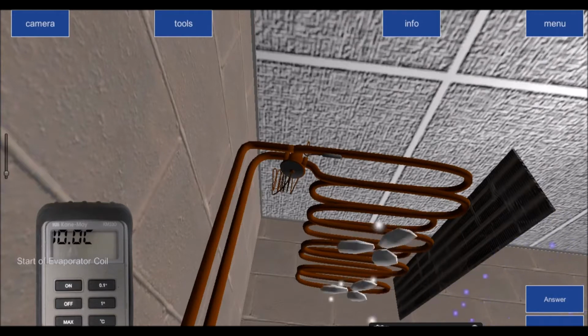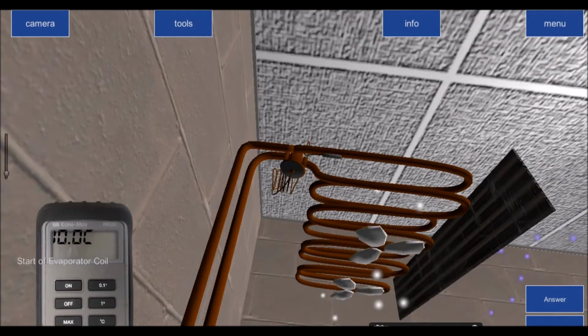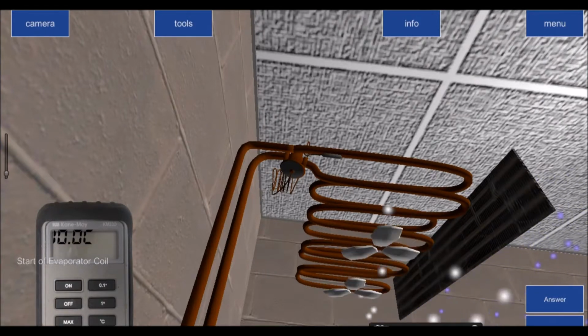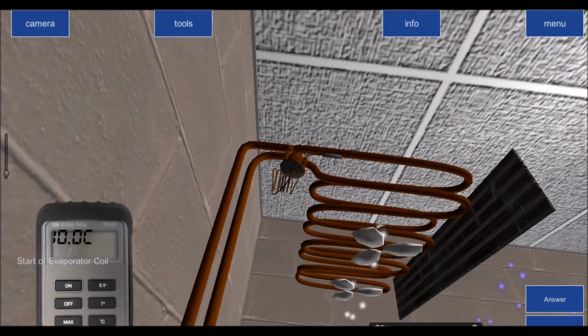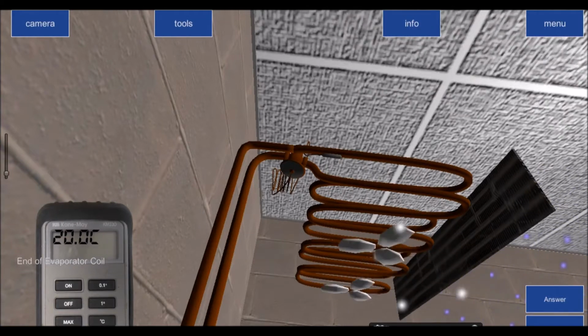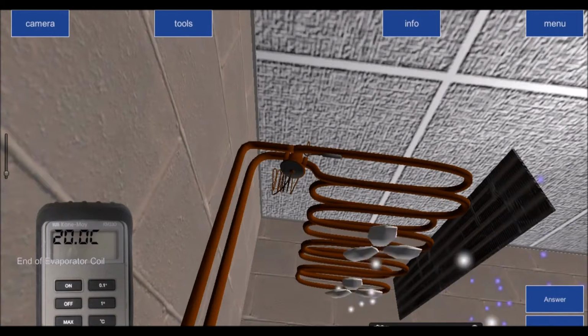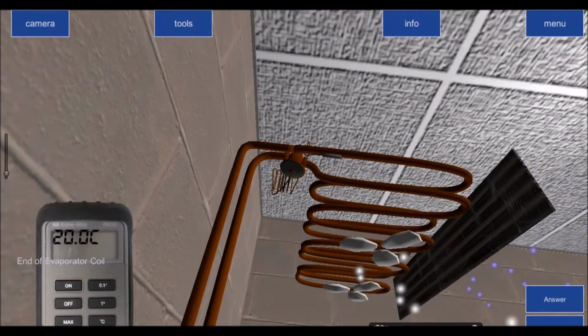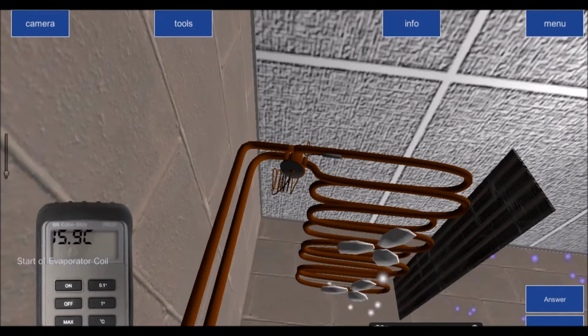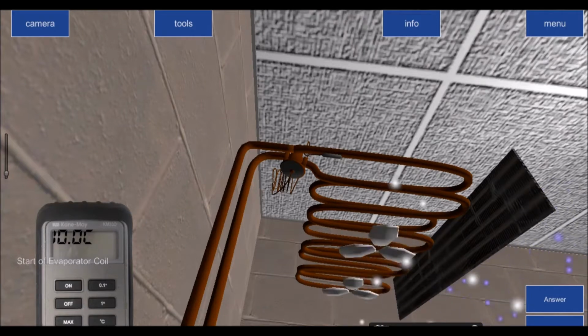So it depends on whether you're bottom or top entry. In this particular case, we're bottom entry here. The expansion device is on the bottom entry. What I would suggest is you try a few different places and then take an educated guess. At the inlet we've got 10. If I take this pipe here, which is the outlet pipe, you see there's 20 degrees. That tells me we have superheated vapor in this section of pipe, whereas this section of pipe is telling me we have saturated vapor, saturated liquid, in this section of the pipe, okay?